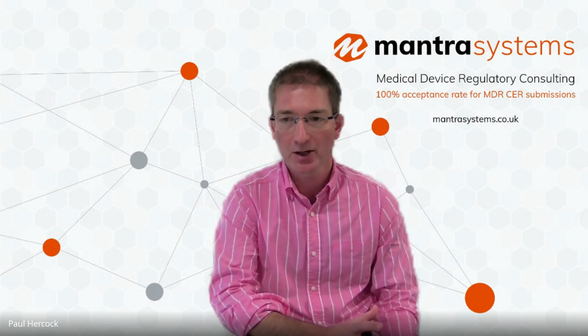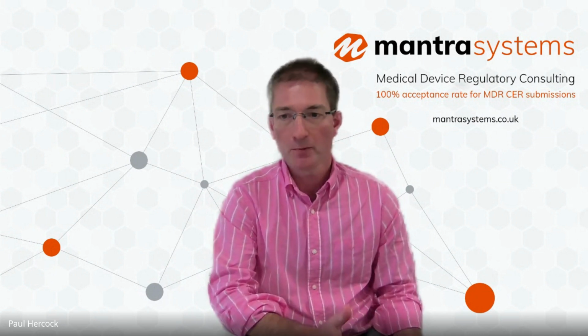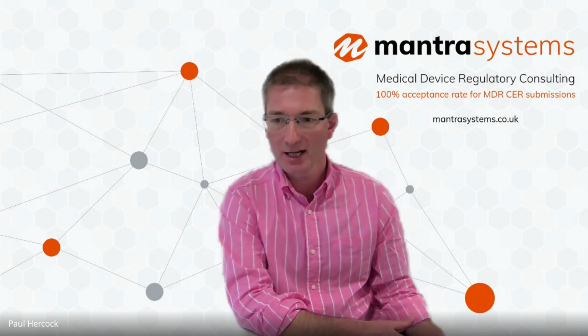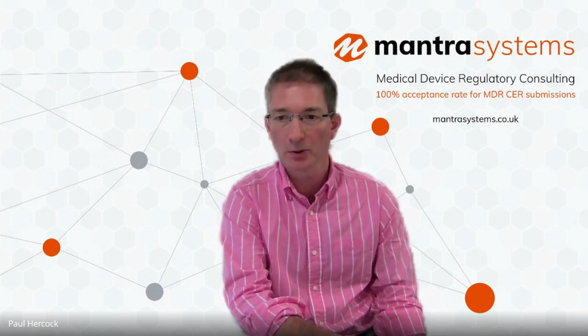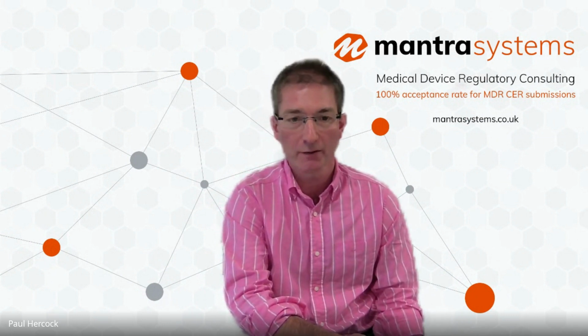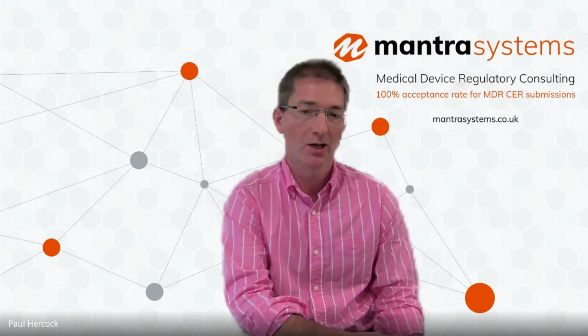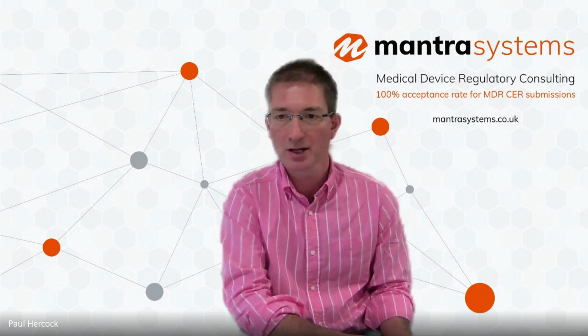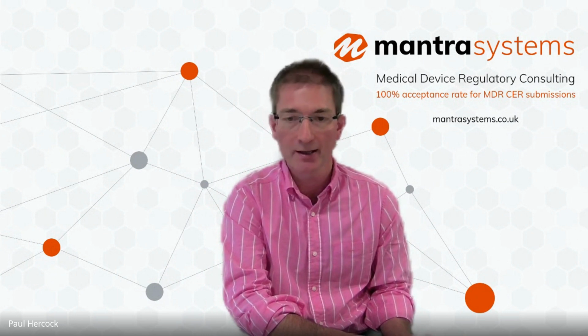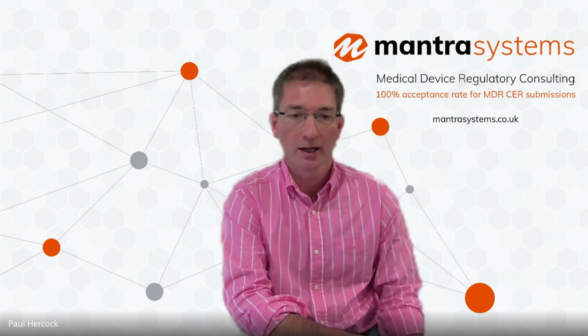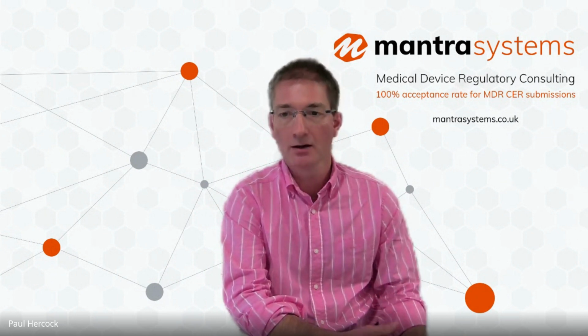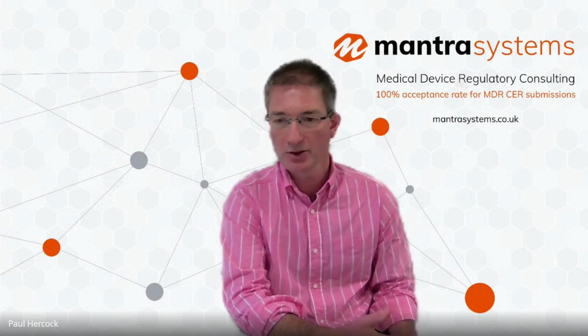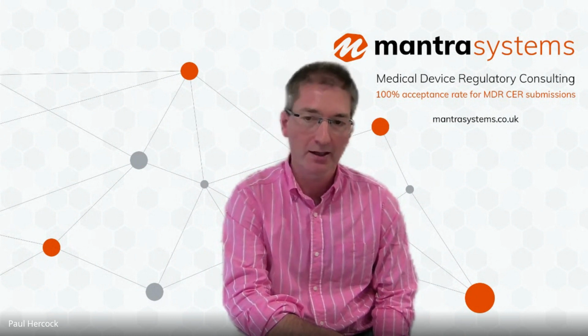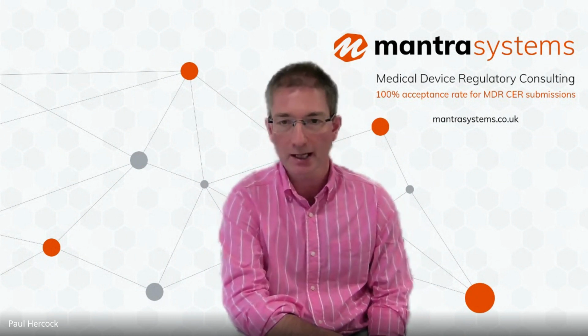And to be honest, Article 61(10) should be considered an edge case. It's not advisable to use that as a route to conformity if you can avoid it, because the regulators will automatically be on notice if somebody presents a 61(10) conformity route. But no, if you have a device which doesn't really neatly fit those criteria we talked about before, then it's a case of accumulating clinical data, really.